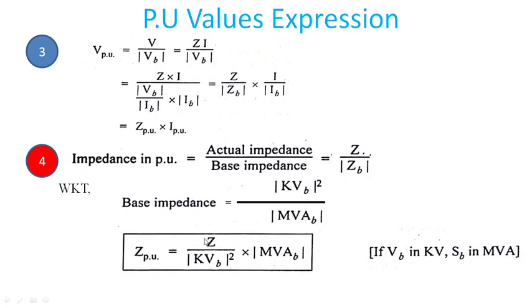So finally you get Z per unit equals Z, the actual value of impedance, divided by kVB squared into MVA. Here we should consider that while substituting voltage and power, voltage should be in kV and power should be substituted in MVA.